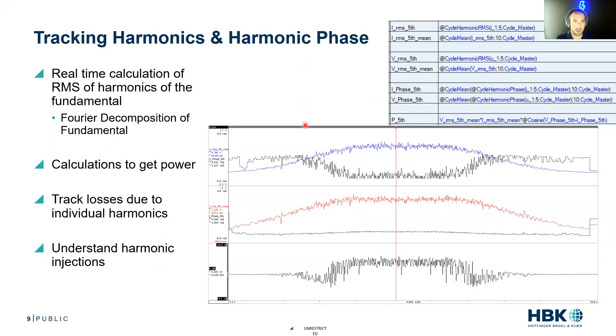Tracking harmonics and harmonic phase. Now this is my absolute favorite because this is the real nerdy one. Sometimes, as I mentioned in that second or third slide, we can create power or losses with our harmonics. Here is an example of tracking the fifth harmonic. In our digital signal processor on our cards in the real time, we can track individual harmonics.